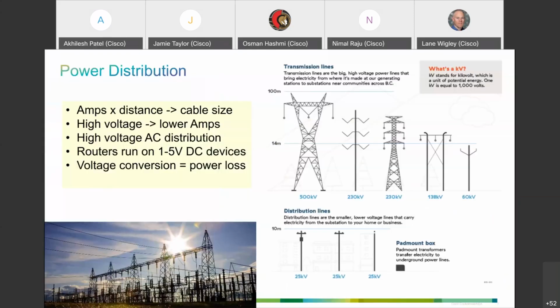I want to take a step back and understand where the power comes from. Power is generated at power plants, and it needs to get from those power plants all the way to our CPUs, our optics, our networking ASICs. As it does that, it goes through a range of different voltages and amperages, sometimes AC and sometimes DC. Usually the beginning of the power distribution is 540 kilovolt AC, and the end of the power distribution is 1 to 5 volts of DC. That's what the components in our routers run on. So how do we get it there?